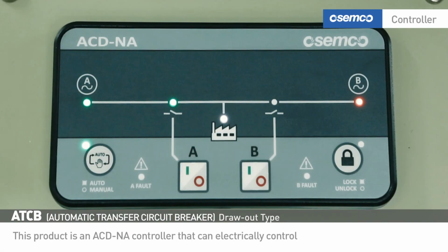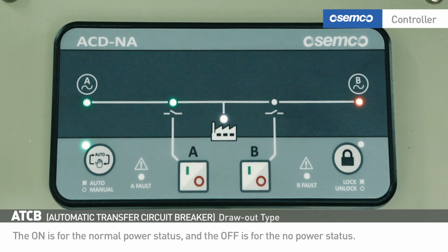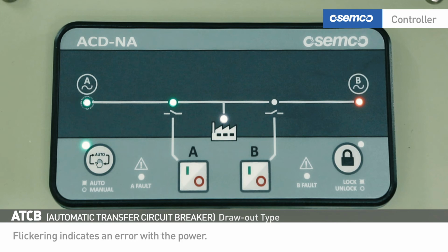This product is an ACD-NA controller that can electrically control the ATCB both automatically and manually. The green lamp indicates the A-side power status. The on is for the normal power status, and the off is for the no power status. Flickering indicates an error with the power. The green lamp shows the A-side input status. The on indicates the input, and the off is for open.